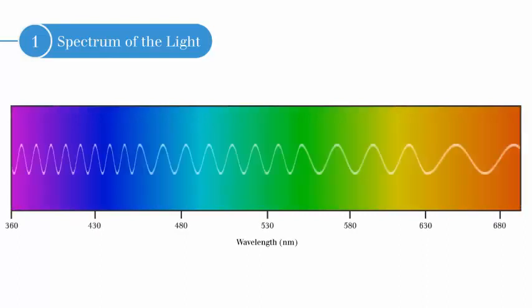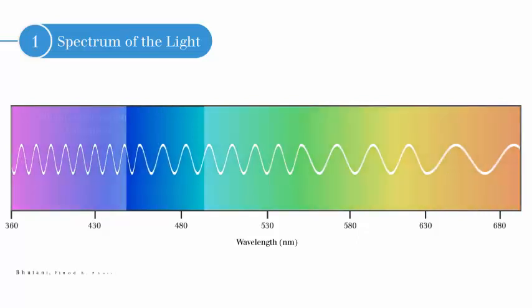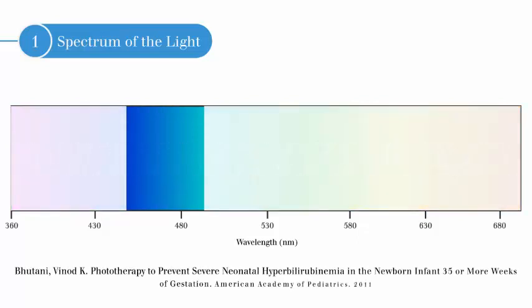The first consideration is the spectrum of light. Light is electromagnetic radiation within a portion of the electromagnetic spectrum. Specific wavelengths of visible light trigger photoisomerization and oxidization. Blue light, the light responsible for breaking down bilirubin in jaundiced babies, is most effective at a wavelength of 460 to 490 nanometers, per the latest reports from the American Academy of Pediatrics.